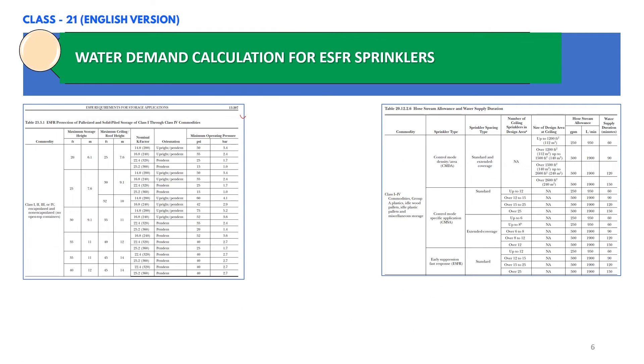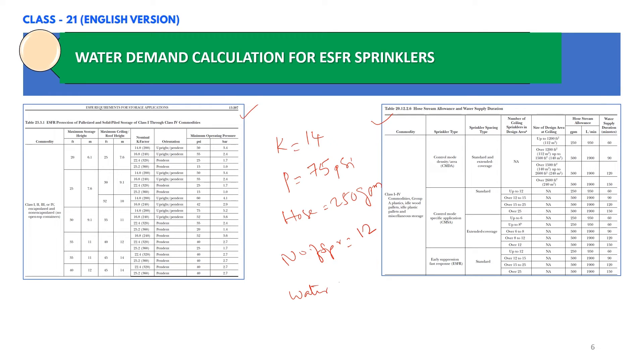Let us note down all the values we have determined: K factor is 14, minimum operating pressure for one sprinkler is 75 PSI, hose stream allowance is 250 GPM, number of sprinklers to be considered is 12 as per NFPA 13, and the water supply duration required is 60 minutes. In the next slide we are going to calculate the water demand requirements.